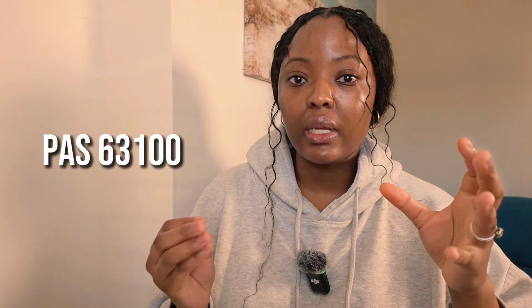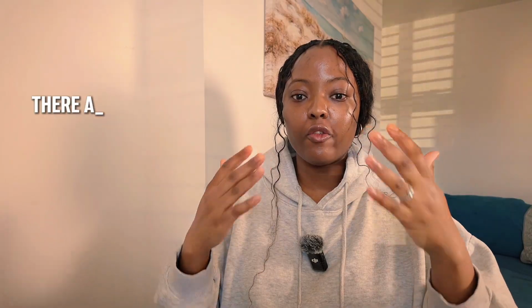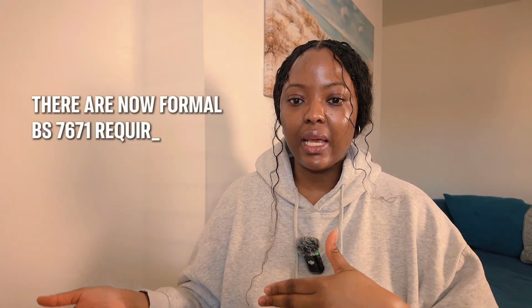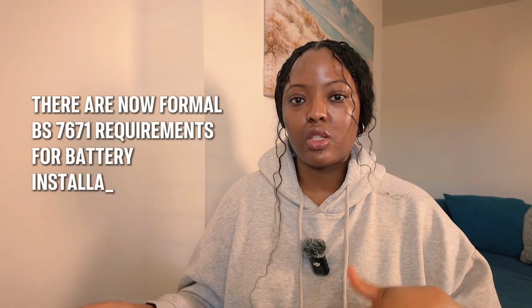For domestic battery installations, there's a specific reference to PAS 63100, the standard for protecting against fire in battery energy storage systems. For non-domestic buildings, you'll need to base your fire protection measures on a proper fire risk assessment. The key takeaway here is you can no longer just follow the manufacturer's instructions and call it a day - now there's a formal BS 7671 standard or requirement for battery installations.